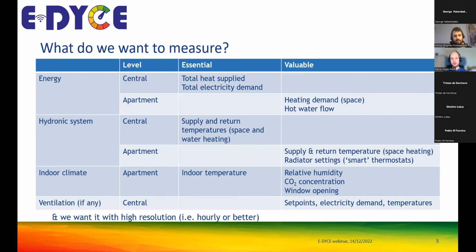At apartment level, we're also interested in supply and return temperatures for space heating, because in a district heating context, good balancing of the different heating systems within apartments is critical to ensure a good return temperature level and efficient operation within the district heating system, as well as radiator settings, which we can get through smart thermostats.